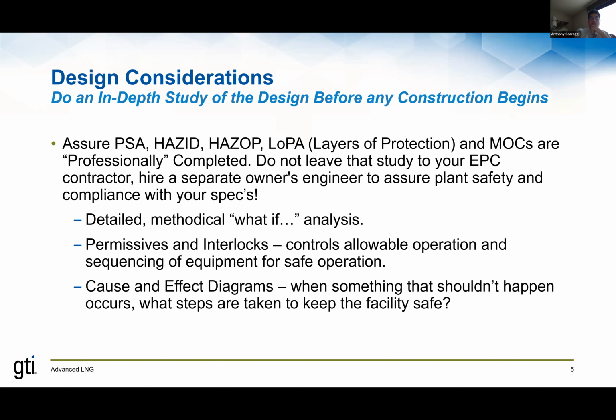Design considerations. When you're building an LNG plant, be sure that you've got professionally done hazard identification, process safety analyses, and layered protection systems to protect the public, to protect the facility, and to protect the equipment from any kind of mishap or human error that could possibly occur. So LNG facilities, just like any other plant, have their own specific hazards. And just like any facility, if they're not operated properly or not designed properly, there could be safety concerns. And you eliminate those upfront in the beginning in your design by using these various processes.